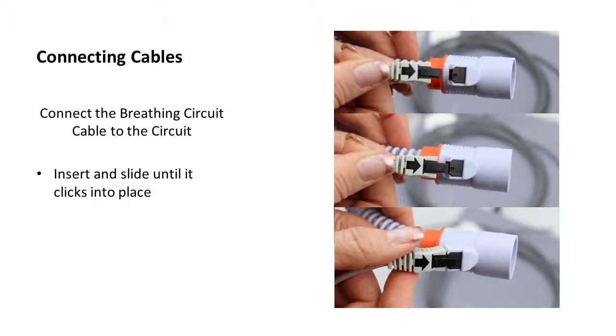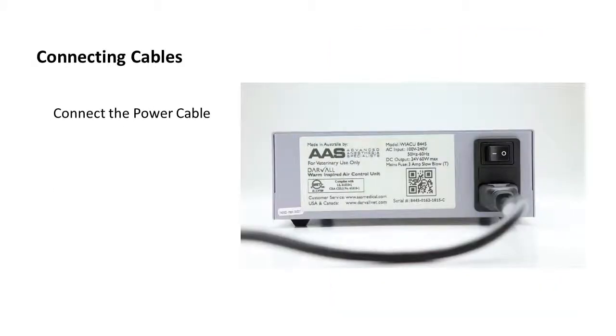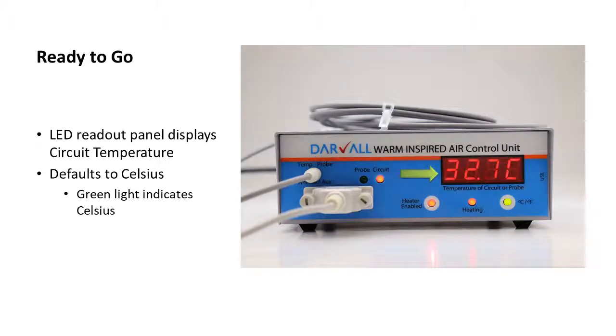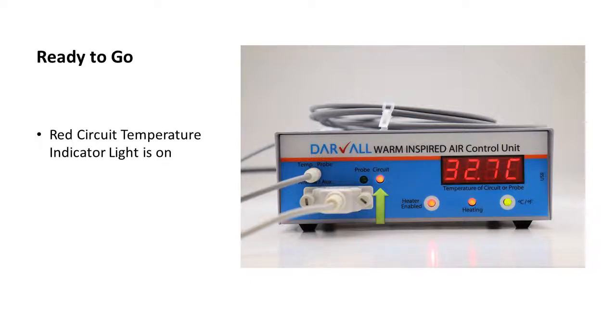Once you've confirmed the cable locking tab is intact, insert the cable connector into the receiver in the circuit and slide it into place as shown until it clicks into place. Connect the power cable into the back of the warm air control unit and plug it into the wall. Now you're ready to turn on the warm inspired air control unit. When you turn the control unit on, the LED readout panel displays the circuit temperature in Celsius. Notice the red circuit light is on. That tells you that the temperature displayed in the readout panel is the temperature of the circuit.